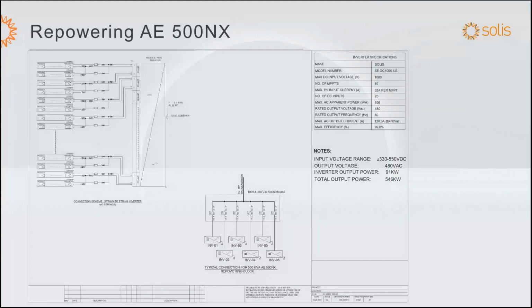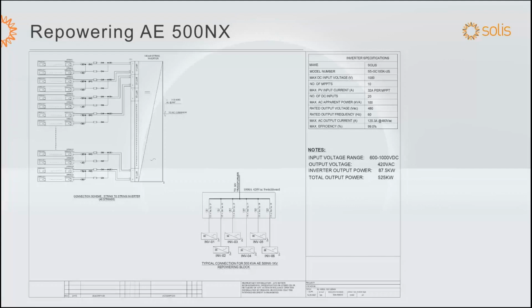The same approach here, as shown in the previous examples, we take in 4 strings per MPPT maximum that could be combined, depending on the string design, that could be connected to the inverter. So far, in most cases, I haven't seen an issue. 40 strings, usually it's more than sufficient to connect to a single inverter from the current combiner boxes, and then we can connect it to AC switchgear and then go to the transformer. Similar matter here with the AE 500 NX 1 kV.